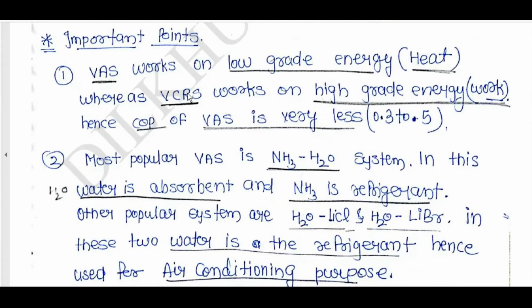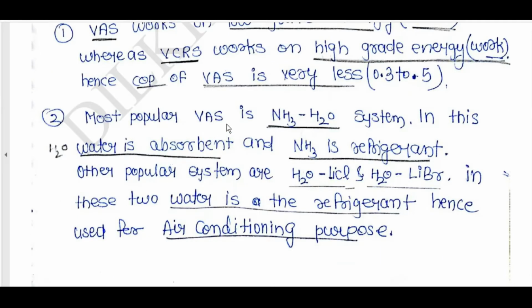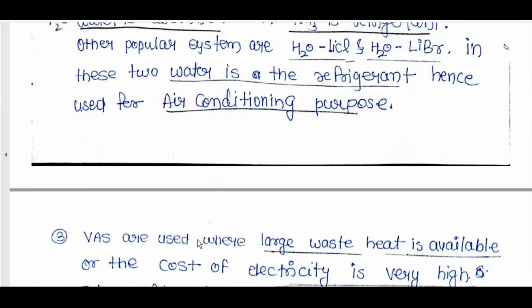Important points: VAS works on low grade energy, that is heat, whereas VCRS works on high grade energy, that is work. Hence the COP of VAS is less, 0.3 to 0.5. The most popular VAS is the NH3 H2O system. In this, water is the absorbent and NH3 is the refrigerant. Other popular systems are H2O-LiCl and H2O-LiBr. In these two, water is the refrigerant and hence they are used for air conditioning purposes.